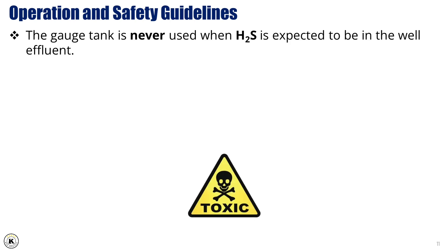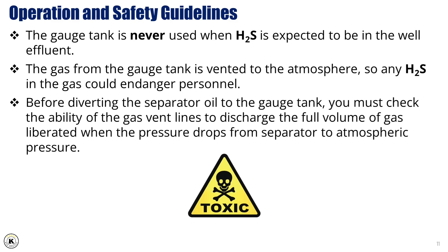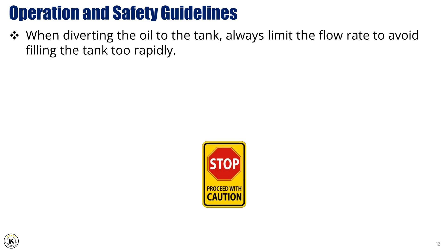Operation and safety guidelines. The gauge tank is never used when H2S is expected to be in the well effluent, as the gas from the gauge tank is vented to the atmosphere, and any H2S in the gas could endanger personnel. Before diverting the separator oil to the gauge tank, you must check the ability of the gas vent lines to discharge the full volume of gas liberated when the pressure drops from separator to atmospheric pressure. When diverting the oil to the tank, always limit the flow rate to avoid filling the tank too rapidly, which can be dangerous and difficult to control.